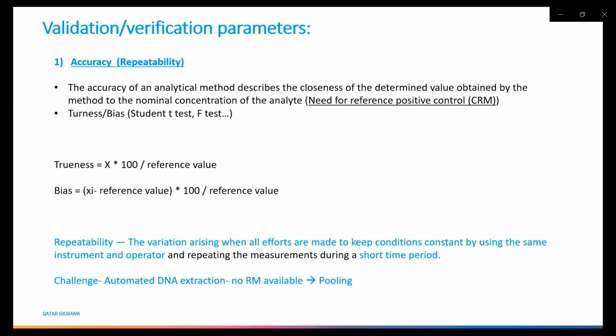For accuracy, it's important to use a good reference method or reference material. It can be a CRM, an RM, or your PT standard, and this will be used as your nominal value. You can use the Student t-test, F-test, or anything with which you can quantitatively express accuracy in terms of trueness and bias. Accuracy is leading to repeatability.